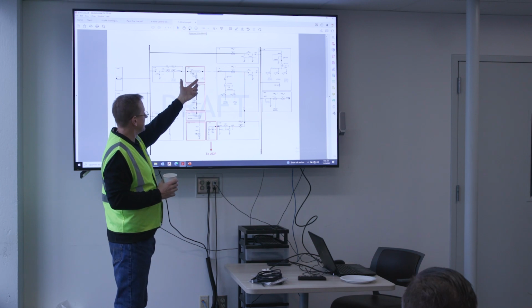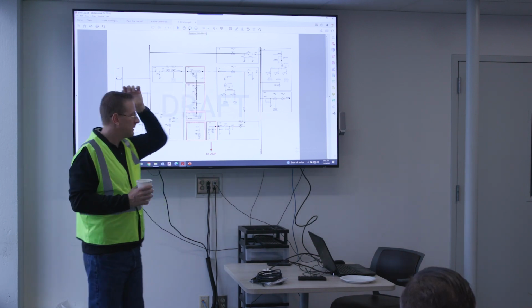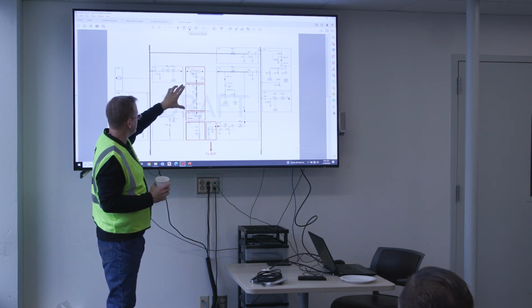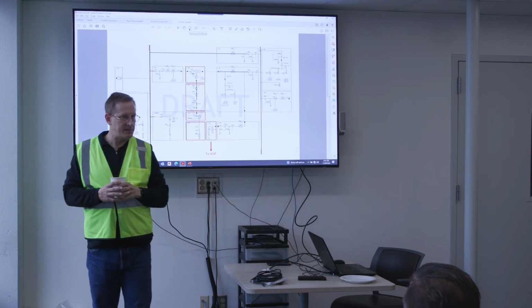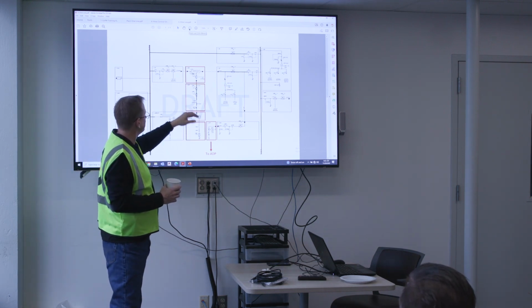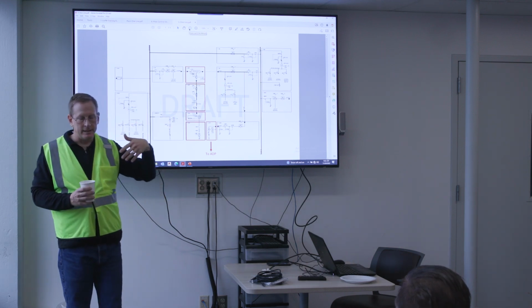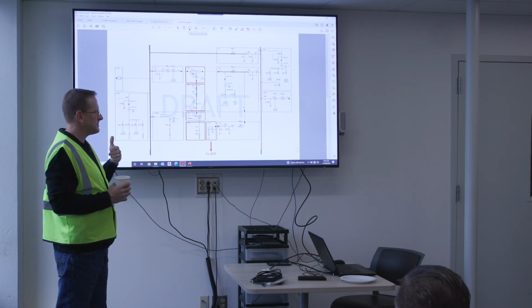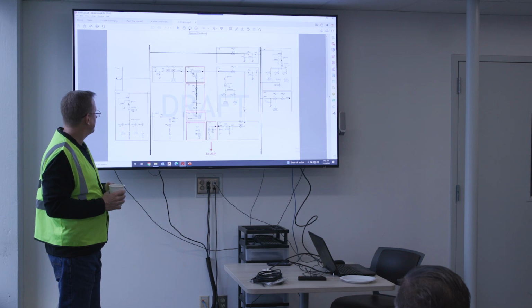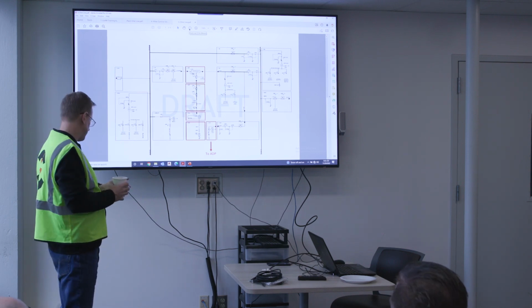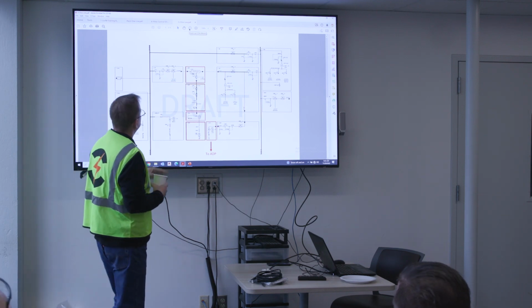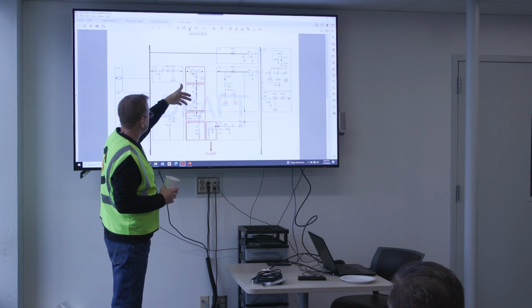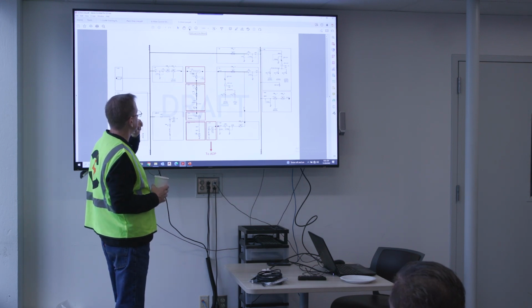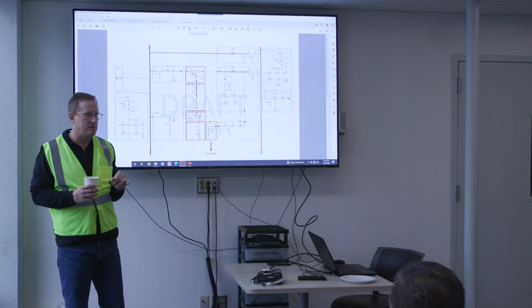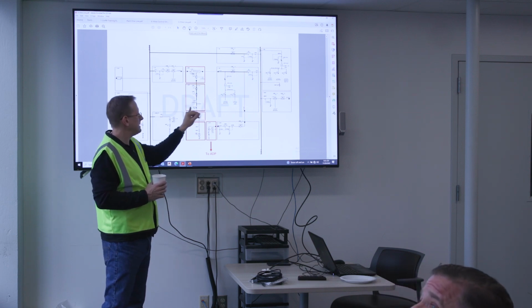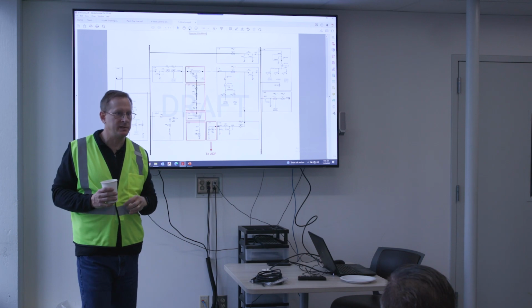And then we have our URP, which again is our choke. URP stands for Unit Reactor Panel. And that's going to feed through the tapping through a GDP, which is our Generator Disconnect Panel, which is simply a disconnect between the generator output and the choke. Okay, so you can actually open that GDP if need be when the system is down. If you want to, power down the system, make sure there's no voltage on the choke, for example. But that's the GDP, and again, it's just more or less a disconnect, but it's got some CTs on it for measuring purposes, for current measurement, and so forth. It's also actually a fused disconnect, so it does offer some protection should it need to have an overcurrent condition that will blow those fuses. So it does provide some protection as well.